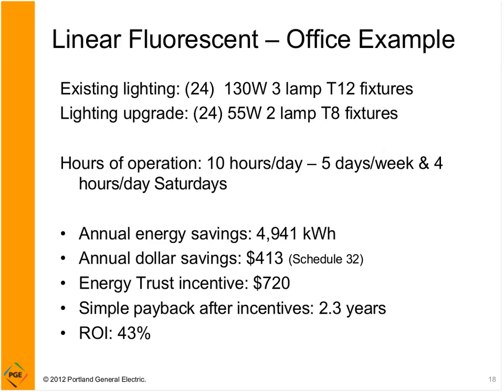So we'll look at a typical office retrofit. So let's say this is a small office. It has 24 130 watt 3-lamp T12 fixtures, and the lighting upgrade or retrofit would be retrofitting these 24 fixtures with a 55 watt system, 2-lamp T8 lamp and ballast combination. And we would plug in some hours of operation, 10 hours a day, 5 days a week, plus 4 hours a day on Saturdays.